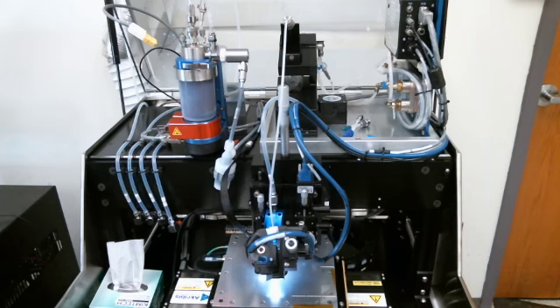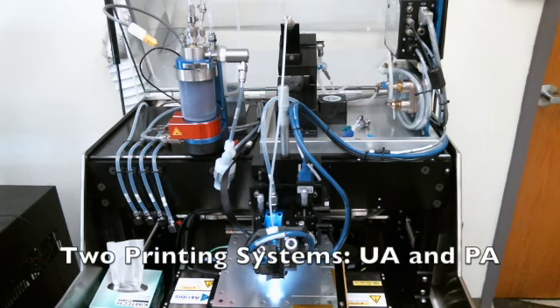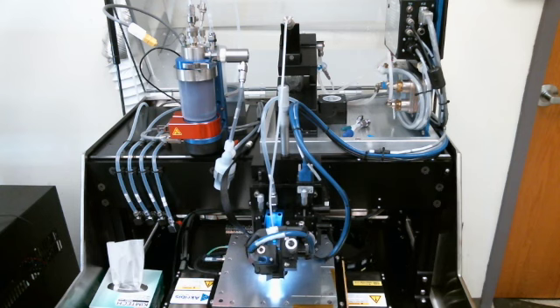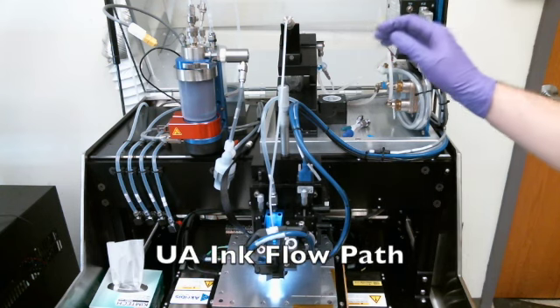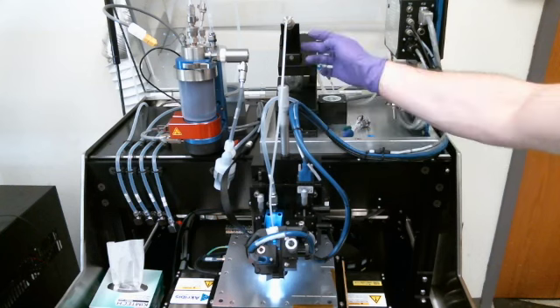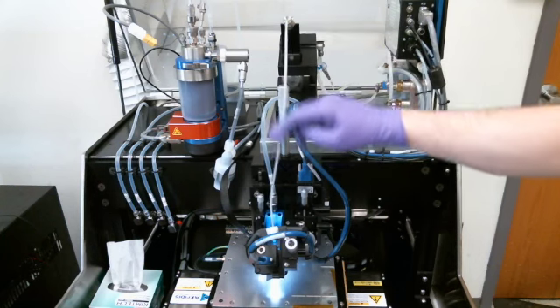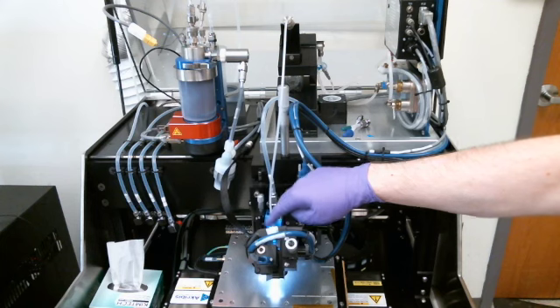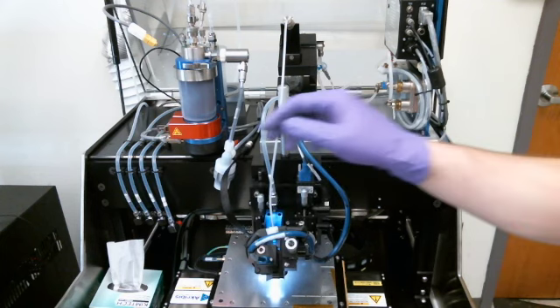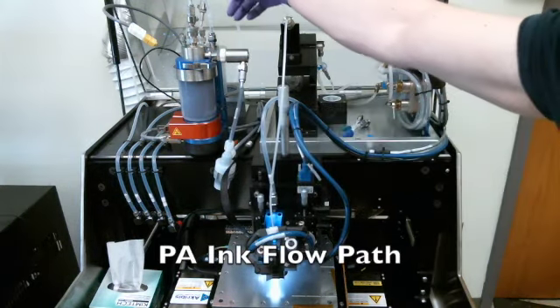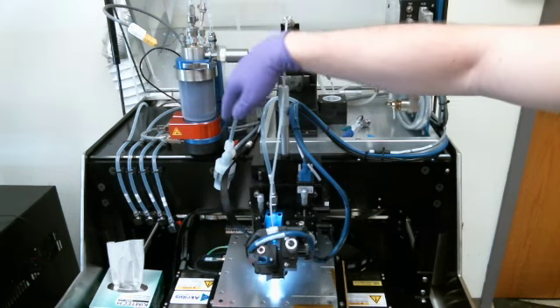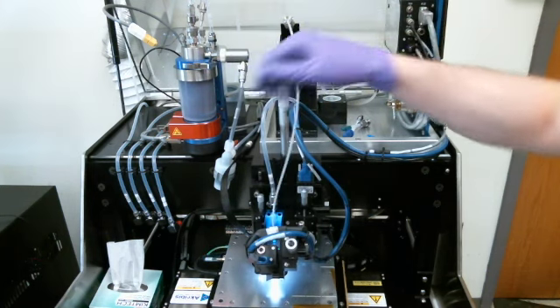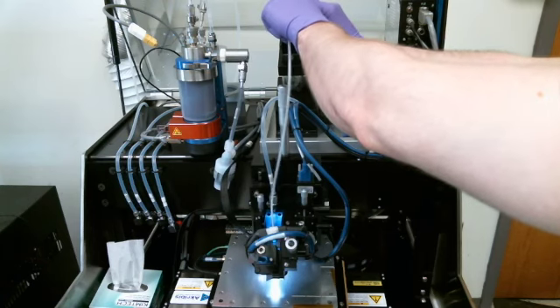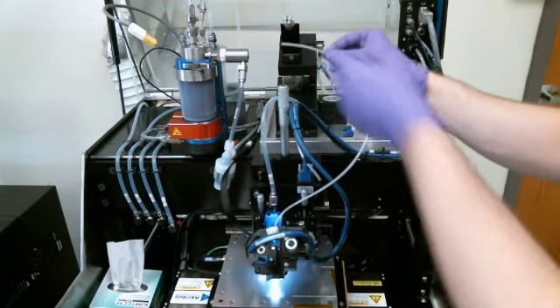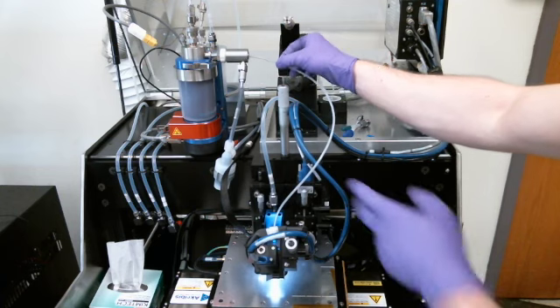So the AJ200 system contains two printing systems, one being the ultrasonic atomizer and the other being the pneumatic atomizer. So the ink flow path for the ultrasonic atomizer, the reservoir is in here. The ink comes through the tube, through this assembly, all the way down to the nozzle. The nozzle will be shown later, and it comes out the tip. The pneumatic atomizer, the reservoir is here. The gas comes through all the way through here. It also has an additional exhaust line, which is here. And if we were wanting to switch between the ultrasonic atomizer and the pneumatic atomizers, the ink would be coming through there and into the tube as well.